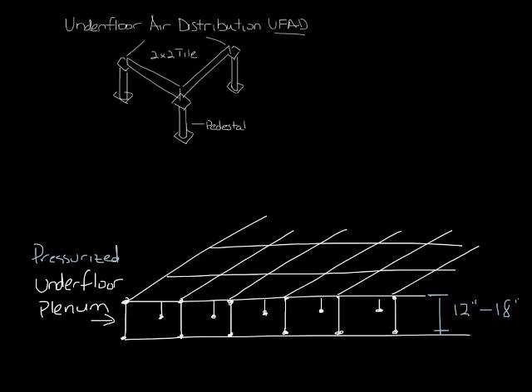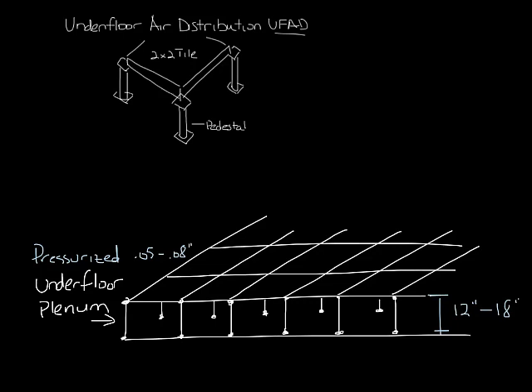We've actually seen some UFAD systems that use VAV boxes and duct work under the floor, but that's not very common, and we're not going to cover that here. The floor is pressurized to between 0.05 and 0.08 inches. And this pressure is maintained by dampers controlled by pressure taps throughout the floor.